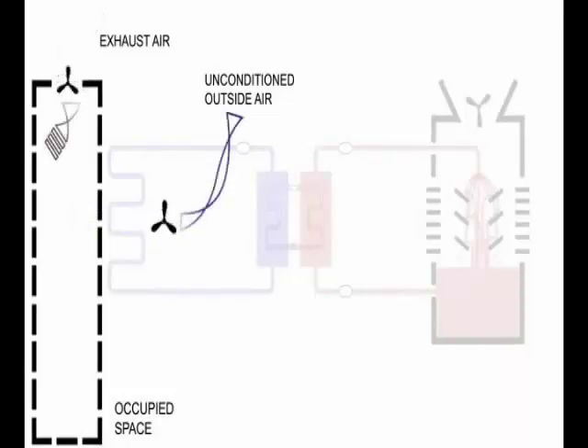When the economizer mode, often called free cooling, is deployed, technicians must be mindful that it isn't too cold. Coils in the air handling unit may freeze and bust, or ice may form in the cooling tower, busting that equipment. Often an economizer cycle is not included in a mechanical package when it really should be. It is free cooling, and even when the economizer mode is available, it is often underutilized by building equipment technicians. That's why it's vital to have the architect, the mechanical engineer, the owner, and the building technician at the table together at the beginning of the design process to get everyone nodding their heads in agreement toward a common goal.